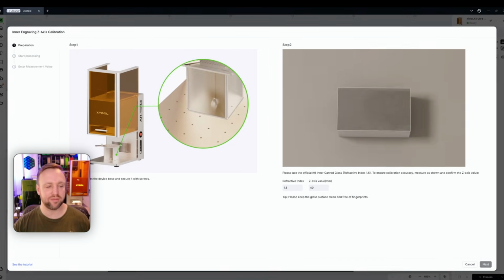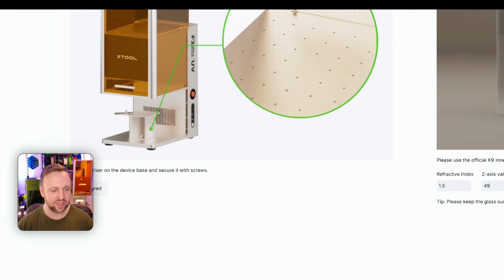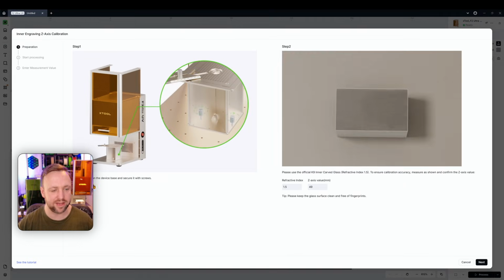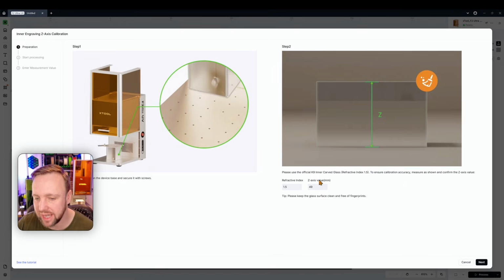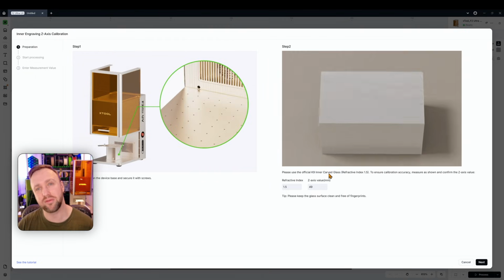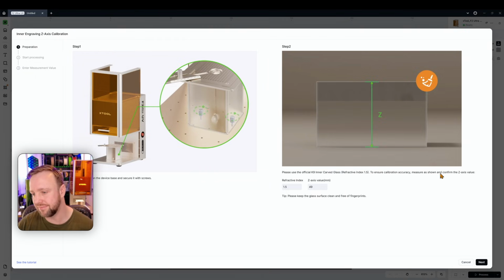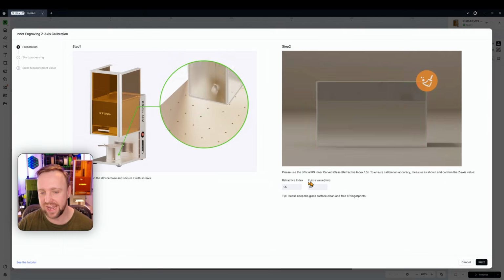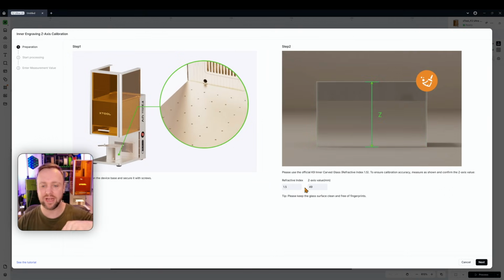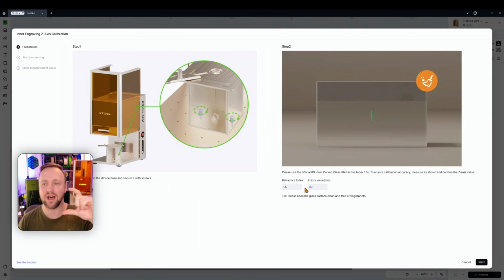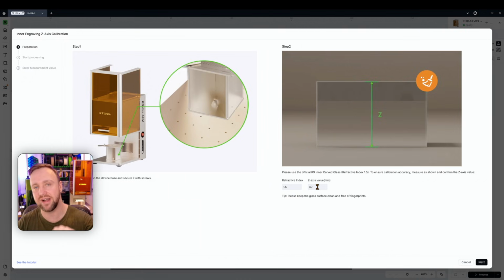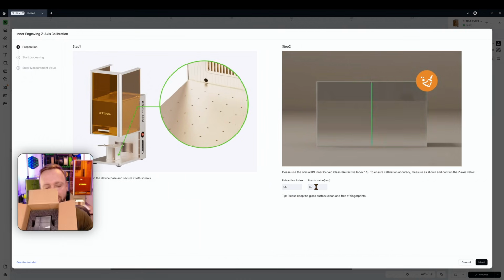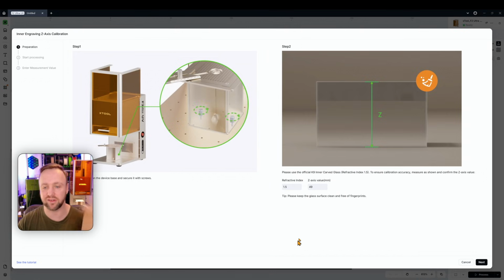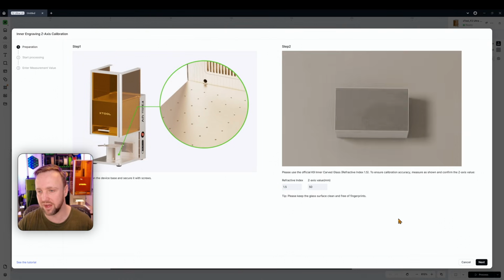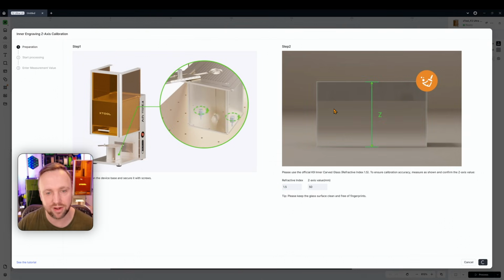So once we've got our platform secured, we are going to tick the secured button just there. Then it's going to say, please use the official K9 inner carved glass. I've just shown you the one I'm talking about. To ensure calibration accuracy, measure as shown and confirm the Z axis value. So what that means is put it in the position it's showing you there, measure the height of it, and then specify what it is. In this case, I have a 50mm high one, so I'm going to change that to 50. The refractive index will stay the same. It is 1.5.